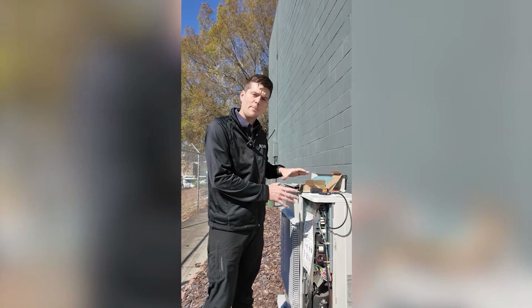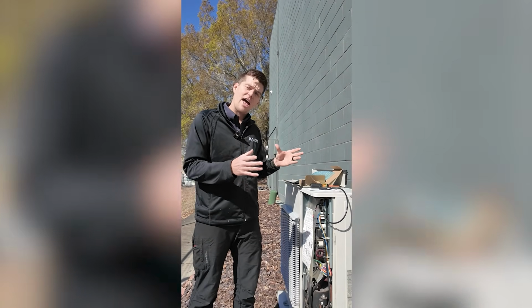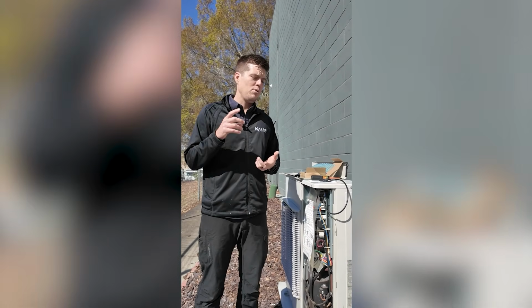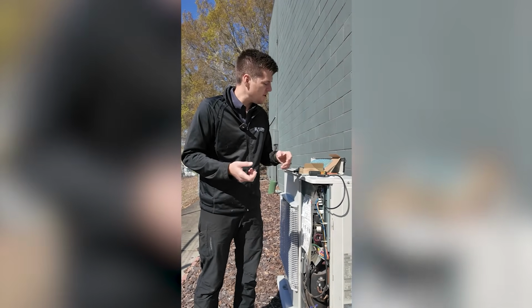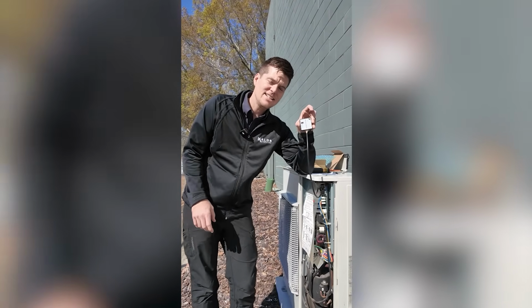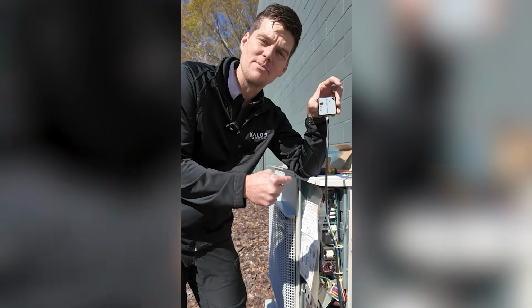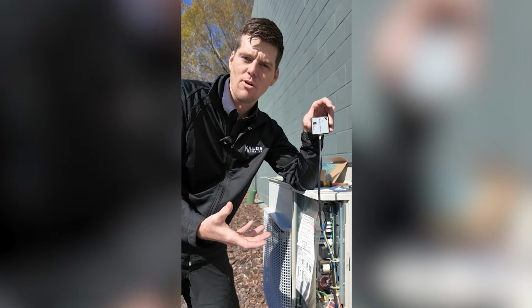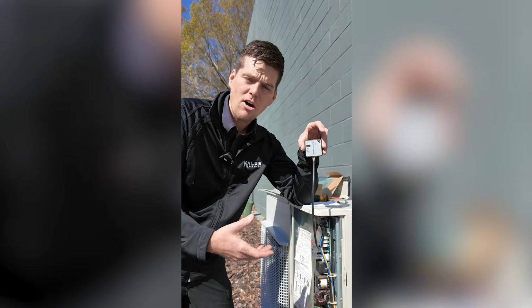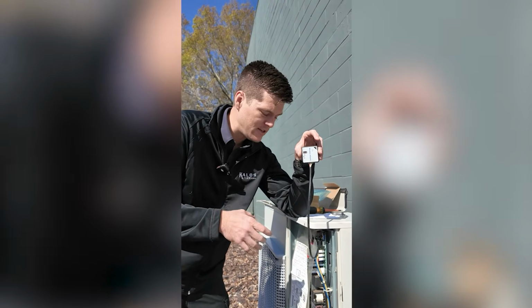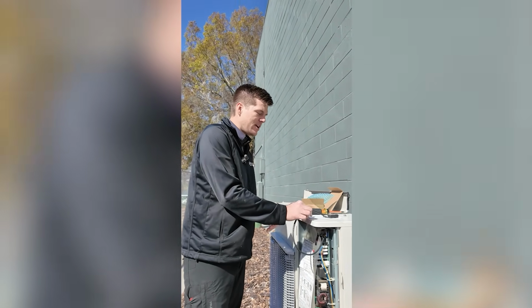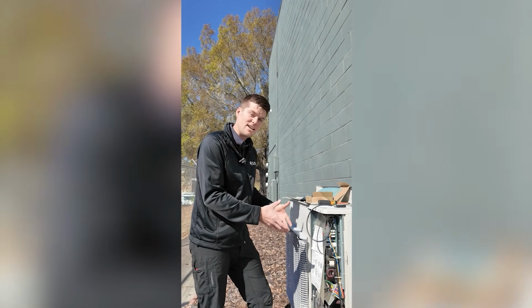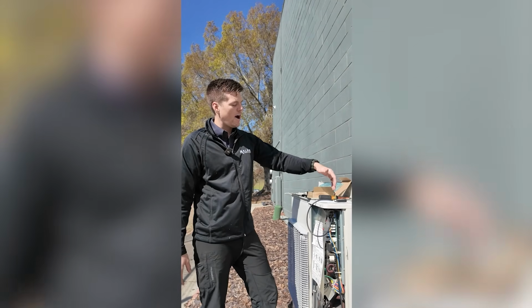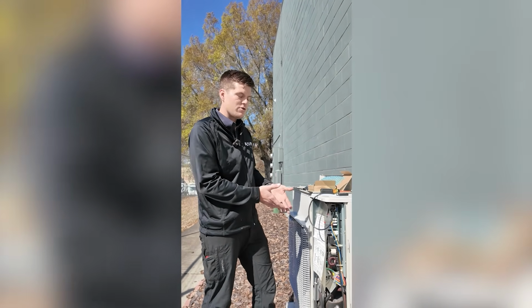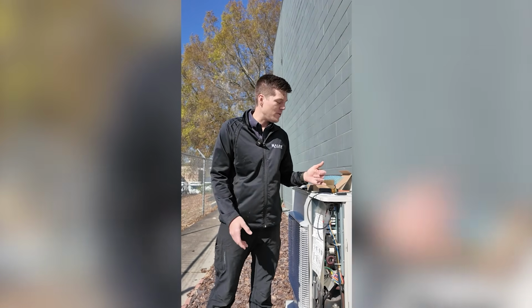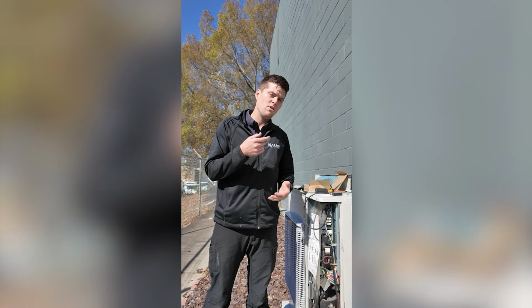But when it comes to system operations with 0 error codes and still having problems maintaining space temp, pulling down on temp, or running for more than 5 minutes, you have to have a service tool like this to gain access to all the information within the system that it sees to understand why it isn't running. Why does it turn off after 5 minutes? All of that information is only accessible through a tool like this on a system like this. You'll have to understand that although you can troubleshoot what you see, there are a lot of unseen things that are required to be viewed to get down to the root cause of why it might be doing something. And so without this, you are sometimes essentially flying blind on equipment like this.